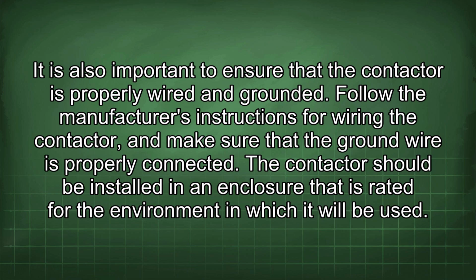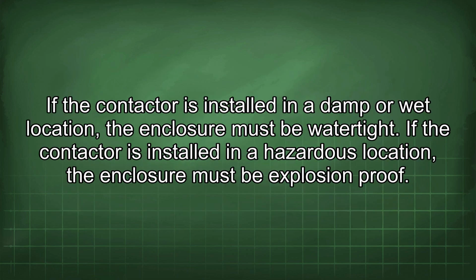It is also important to ensure that the contactor is properly wired and grounded. Follow the manufacturer's instructions for wiring the contactor and make sure that the ground wire is properly connected. The contactor should be installed in an enclosure that is rated for the environment in which it will be used. If the contactor is installed in a damp or wet location, the enclosure must be watertight. If the contactor is installed in a hazardous location, the enclosure must be explosion-proof.